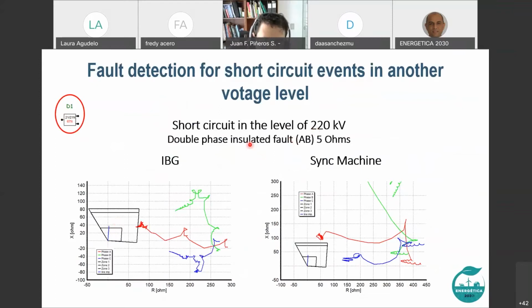Now, as well, at the other voltage level, we were observing the case of a double phase isolated fault in Cuestecitas 220 kilovolts, 5 ohms. We observed that with conventional generation, there is no problem. I mean, as we are used to, the distance protection will not see this fault, and this is the behavior we are expecting. But you can see that when we have inverter-based generation, the impedance is coming from the right and going inside. It could get inside the distance protection characteristic. This is very important because this is different. This is something we are not used to, and we have to take care because it depends on the dispatch of the system and the topology. We can have these faults getting into the distance protection.